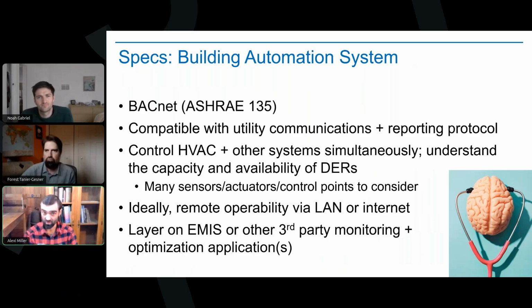Okay, so for the buildings that do have a building automation system, which is probably a large portion, maybe most, almost certainly most of the ones we're modeling, a couple key specs: we want to make sure that BAS is going to be compatible with all the stuff in the building. BACnet helps make sure that happens; that's ASHRAE standard 135.